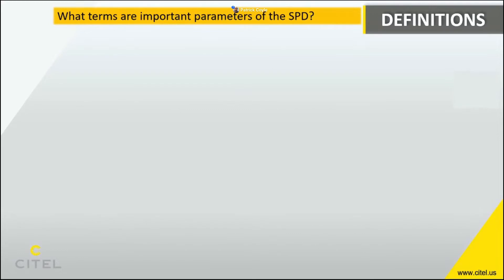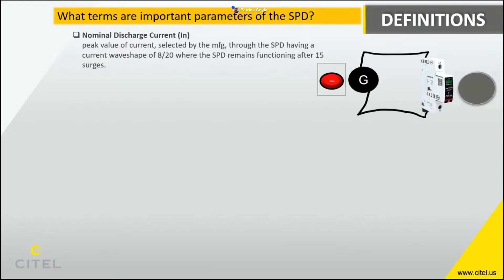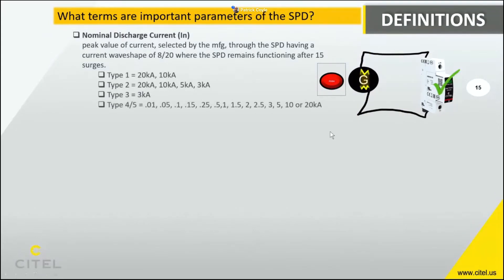There are important terms related to the various UL standards and mandatory codes. The first and very important one is nominal discharge current or In, which comes from UL 1449 in North America. The SPD is connected to a surge generator and hit with 15 impulse shots; if it survives and still works, it passes. Type 1 SPDs are rated for either 20 or 10 kA of In, located closer to the service entrance of the building. The same logic applies for Types 2 and 3 — as we move further into the building, the In is allowed to be lower.